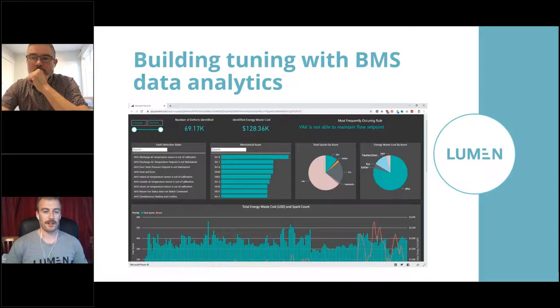It's a relatively new development in New Zealand. But it's a really effective way of continuously finding those hundreds and probably thousands of faults in some buildings and those improvement opportunities in HVAC systems. It works by analysing data on a live basis, polling data every 1 or 2 minutes, and it just runs rules that we set up that we know will find faults. So in the real simple case, it'll say, is the equipment operating when it should be? If not, flag it and let me know so I can do something about it.